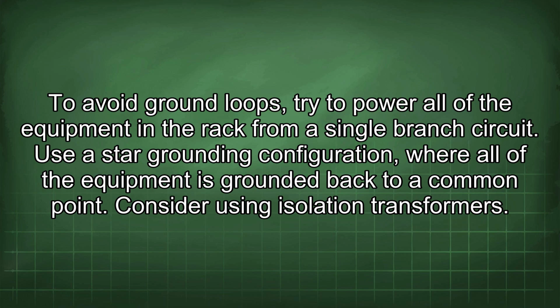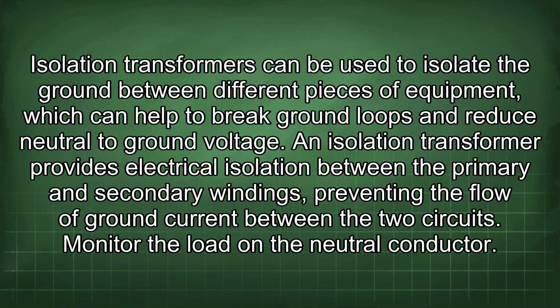Consider using isolation transformers. Isolation transformers can be used to isolate the ground between different pieces of equipment, which can help to break ground loops and reduce neutral to ground voltage. An isolation transformer provides electrical isolation between the primary and secondary windings, preventing the flow of ground current between the two circuits. Monitor the load on the neutral conductor.